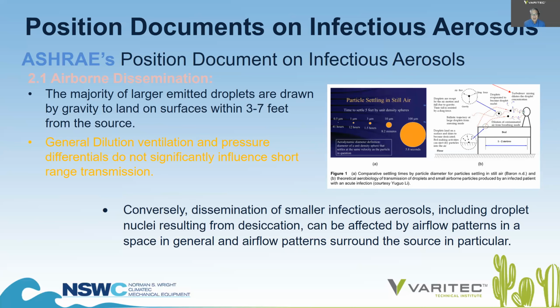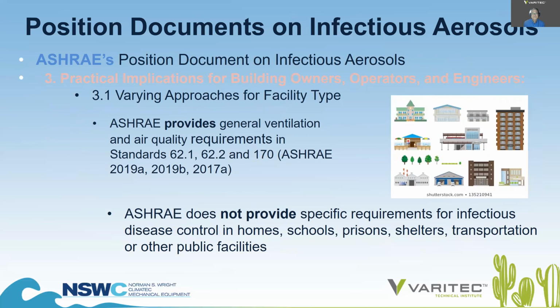However, ASHRAE says, conversely, dissemination of smaller infectious aerosols, including droplet nuclei, which we mentioned, can stay airborne for minutes, hours, or days. Droplet nuclei resulting from desiccation, and we'll cover that in more detail in future, can be affected by airflow patterns in the space in general and airflow patterns surrounding the source in particular.